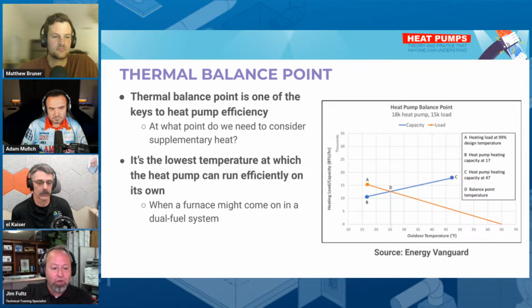And thank you for the slide here. Yeah, there you go. The thermal balance point for capacity: the colder it gets, the less heat, the less BTUs that heat pump's making. And at some point, you're going to have to add another type of heat to be able to take care of the load. So that's the capacity that we're going to.